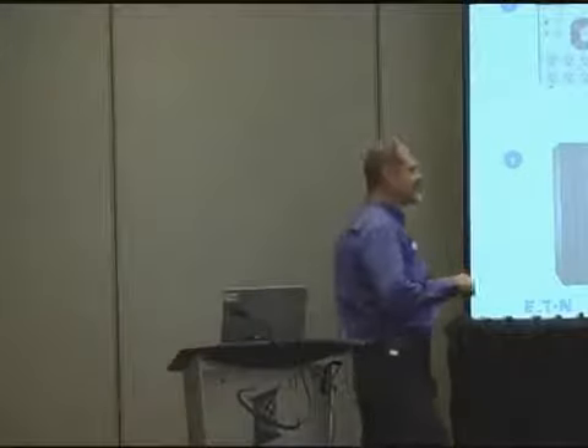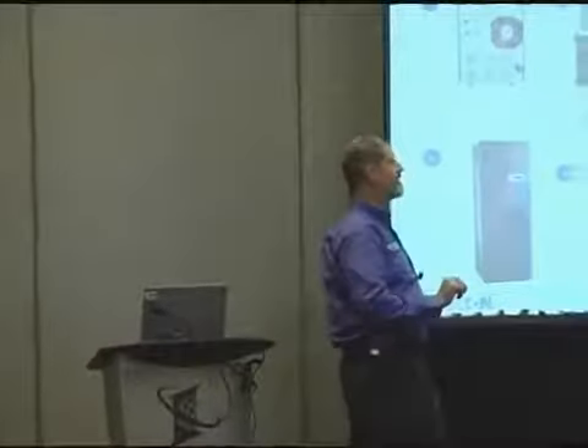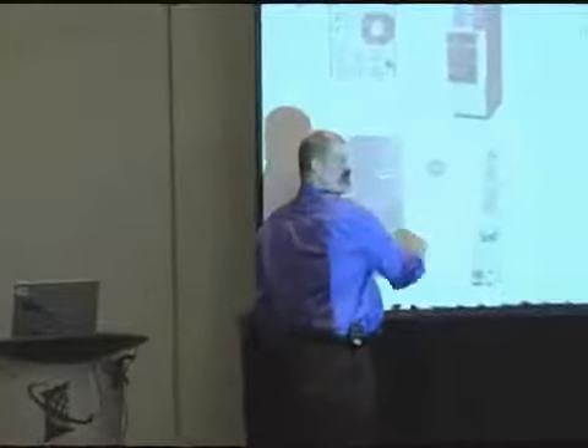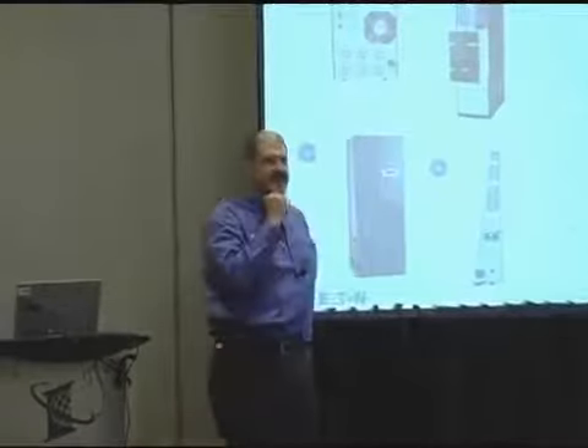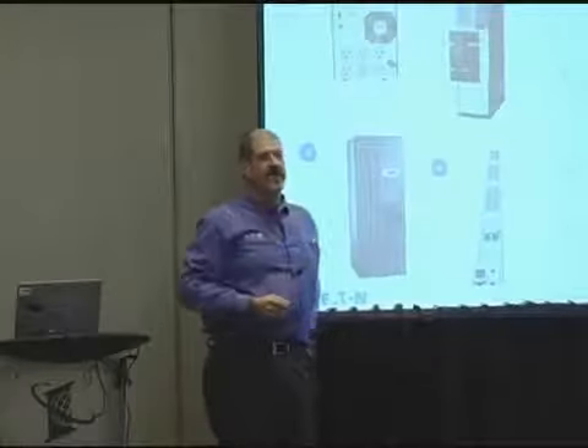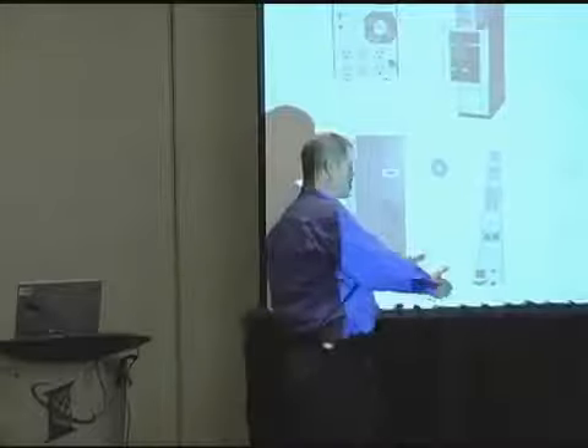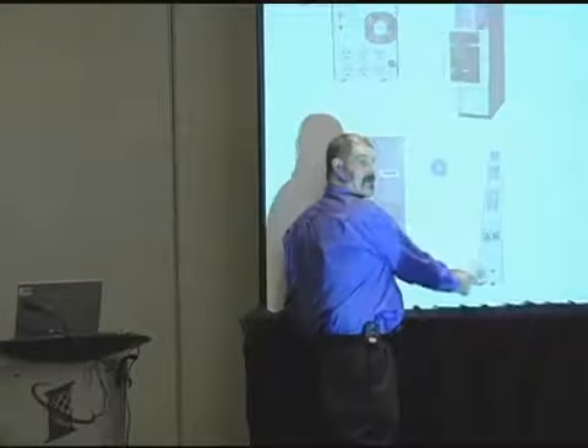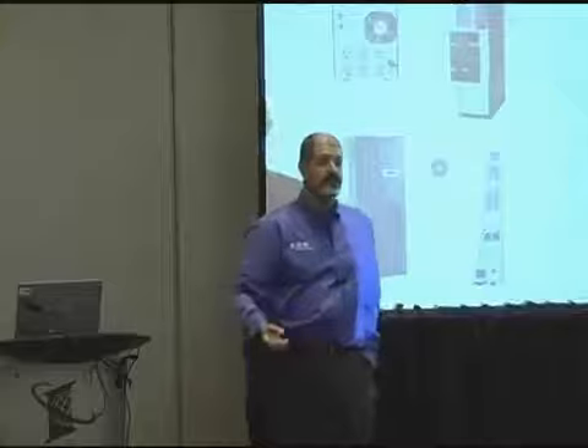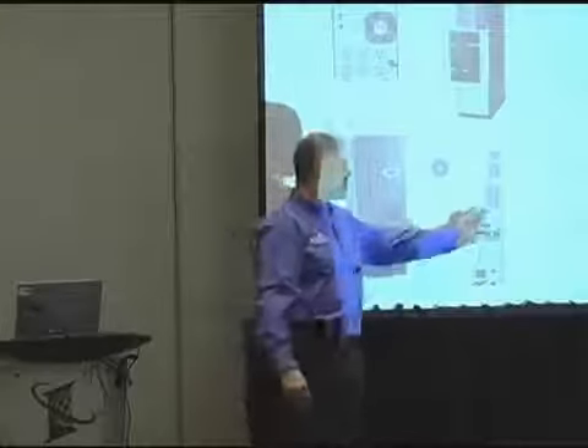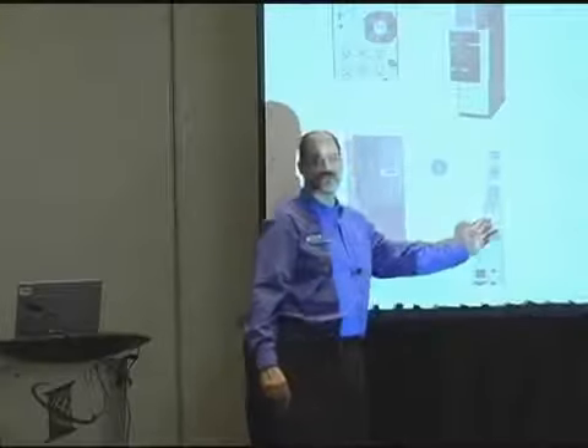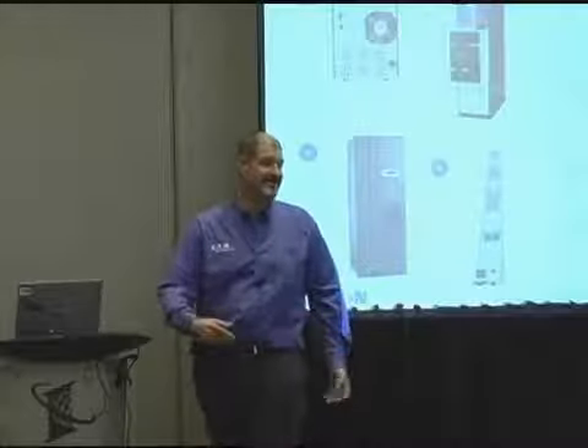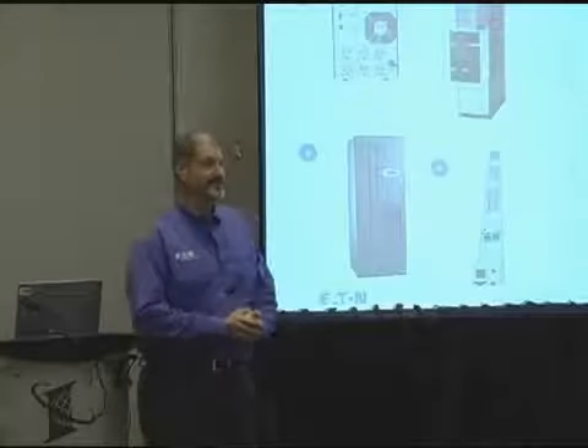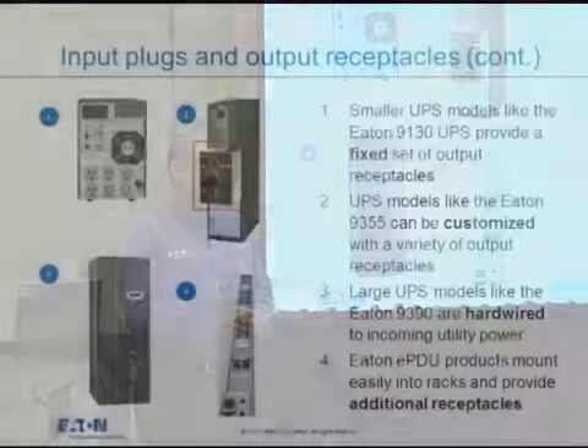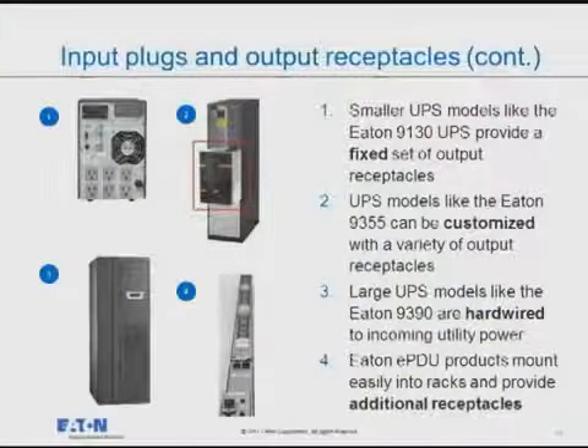And I'll come back to this in a moment, but while I have this slide up here, as I'm introducing all of these touch points, these interfaces, I also introduce the ability to do power monitoring. Most of these vertical power bars have power meters, so I can give you current per phase. Most of these power bars have power meters on the individual receptacles. So I can tell you J14 is drawing 8 amps. I can turn those receptacles on and off, right?